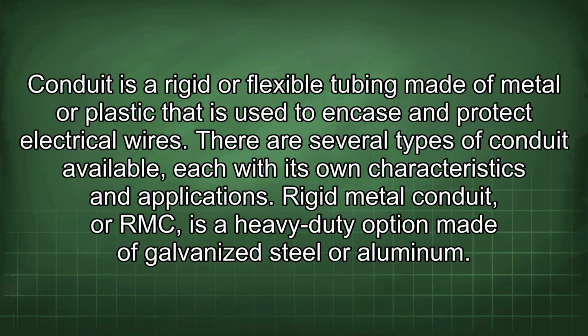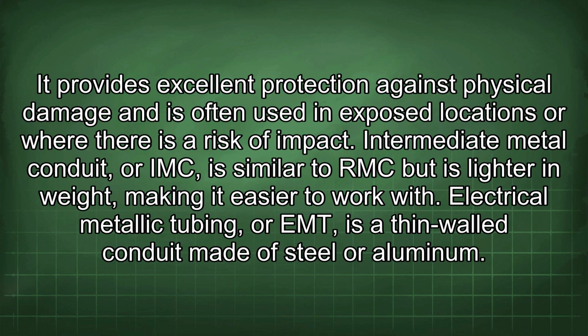Conduit is a rigid or flexible tubing made of metal or plastic that is used to encase and protect electrical wires. There are several types of conduit available, each with its own characteristics and applications. Rigid metal conduit, or RMC, is a heavy-duty option made of galvanized steel or aluminum. It provides excellent protection against physical damage and is often used in exposed locations or where there is a risk of impact.